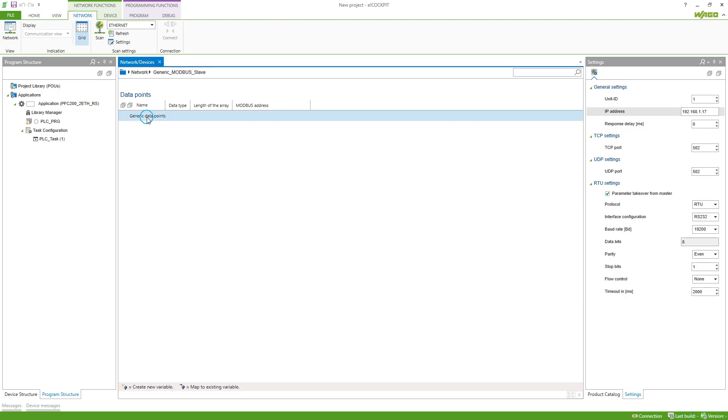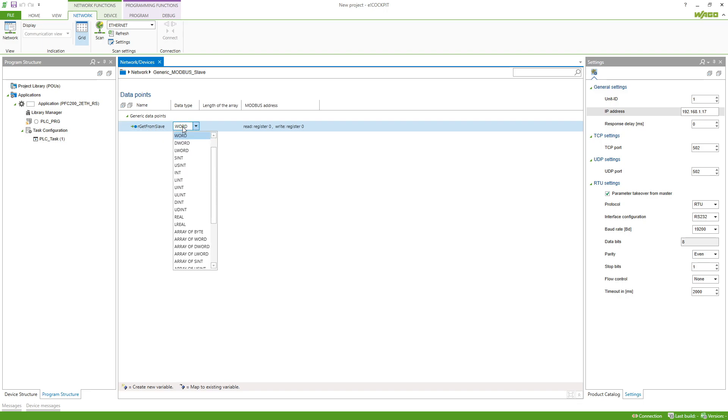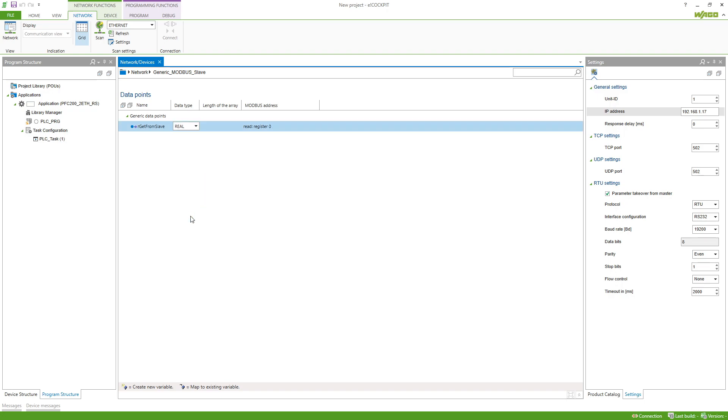So here my Modbus slave has two data points which I have to recreate. I do a right click and then add. The first data point is to get from slave because we want to get this variable from the slave. The name that I type in here can be anything you want this to be named.